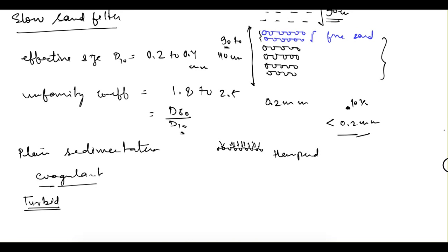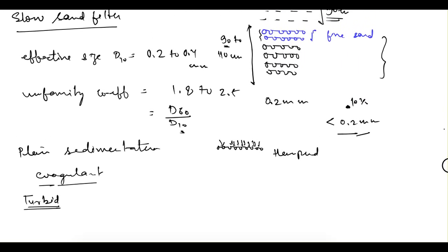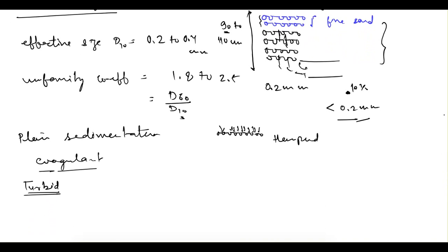Now, talking about the working of these filters, how do they work? We apply the water up to this depth of filter, and then the various processes we have seen take place, and we get the effluent from here. Initially, when we apply the water, we do not use the effluent for up to 24 to 36 hours.